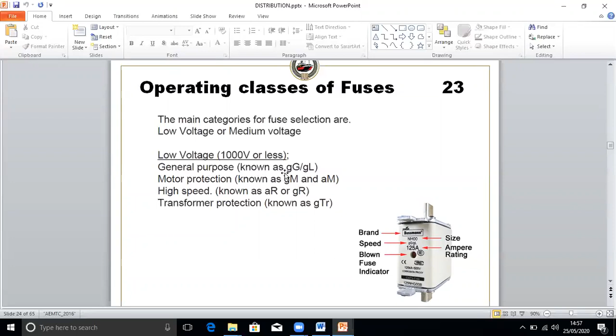So the main categories of fuse selection are low voltage and medium voltage. Low voltage: general purpose fuse, motor protection, high speed and transformer protection. An important point concerning fuses: in the event of a fuse blowing, the cause of the fault must be located. Suppose in a starter the control fuse has blown. Sometimes once you replace it, it's okay. But if it is still blowing, it means there is a short circuit somewhere inside. You have to investigate it.